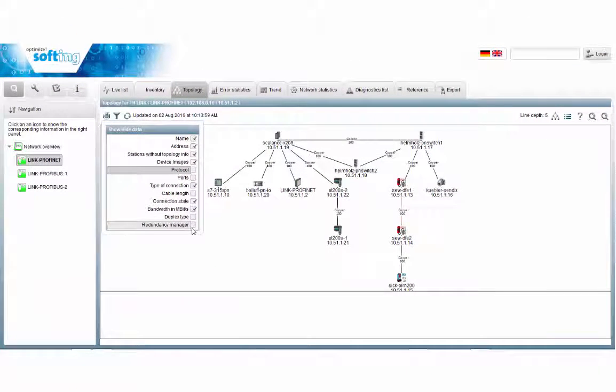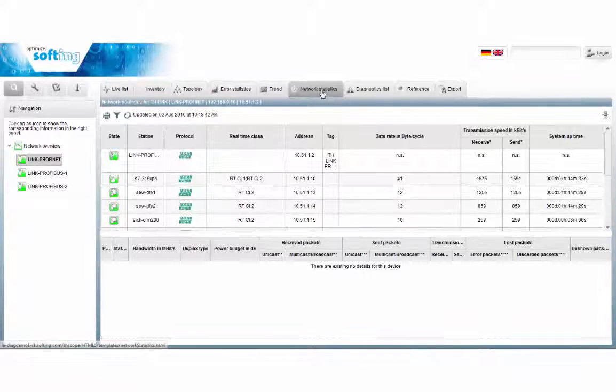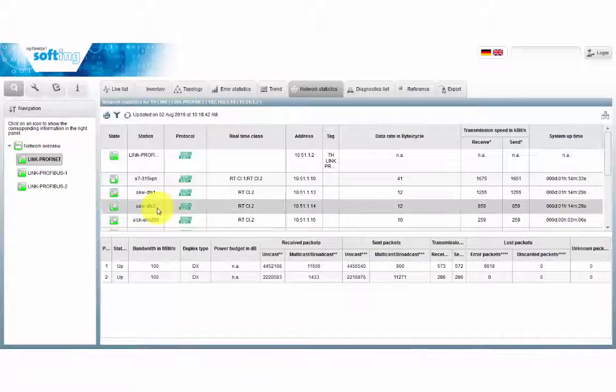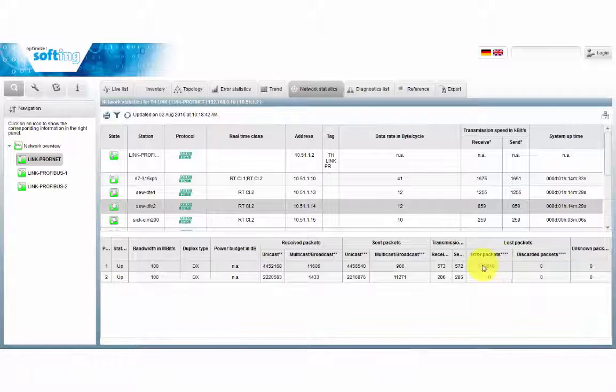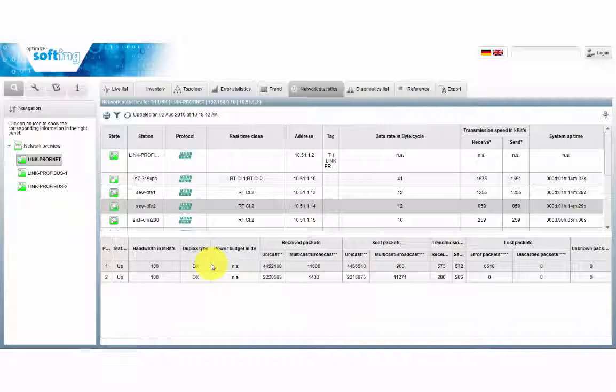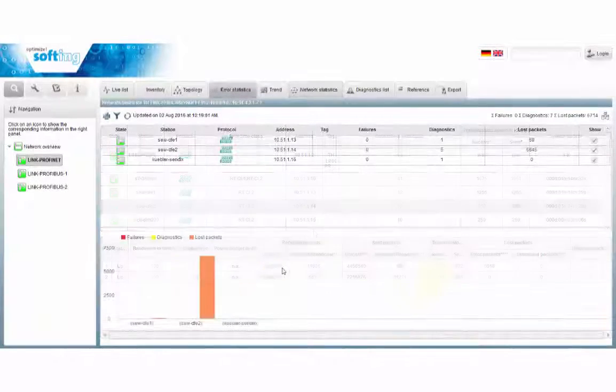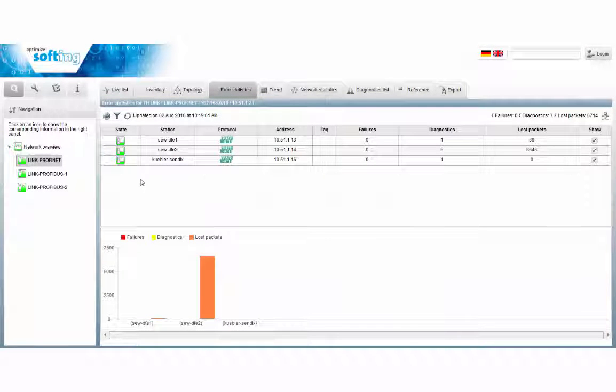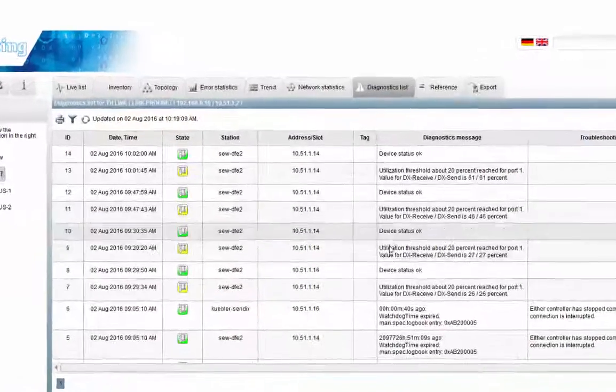In the case of loss packages, you can check the network statistics for the type of problem or loss. Select the appropriate participant — this will lead to more detailed insights at the port level, such as the level of utilization and package losses. In other views of TH-SCOPE you will find information about the frequency of diagnosis and losses, diagnostic messages, and peak loads.